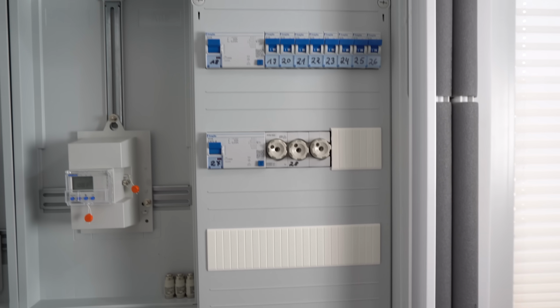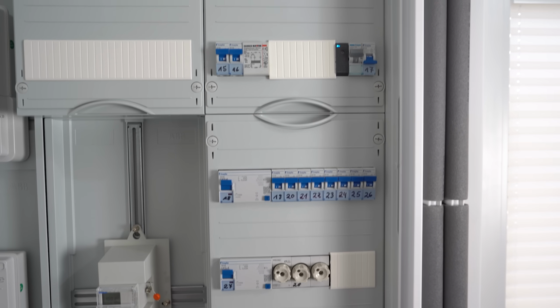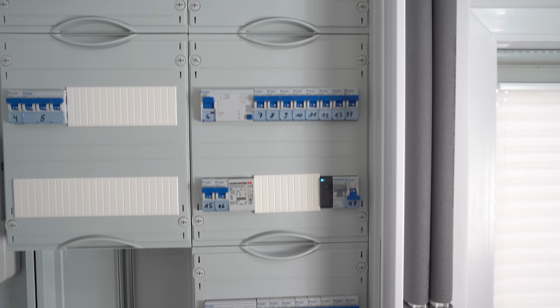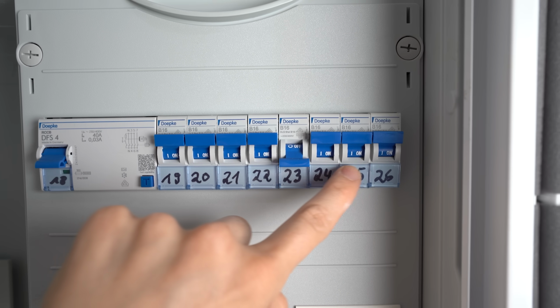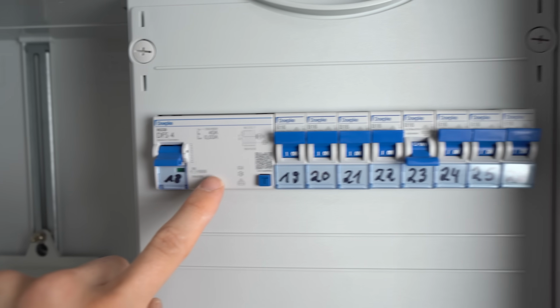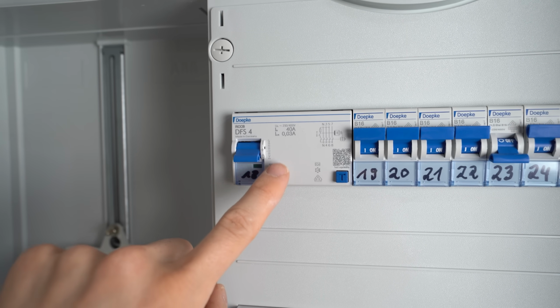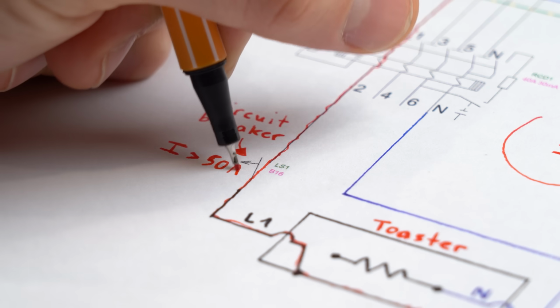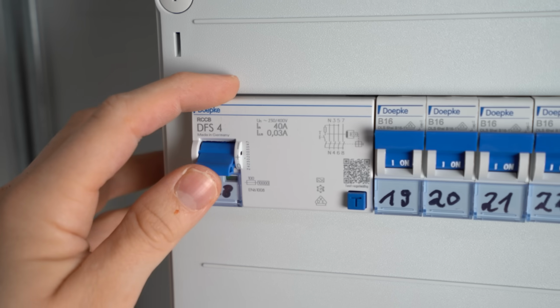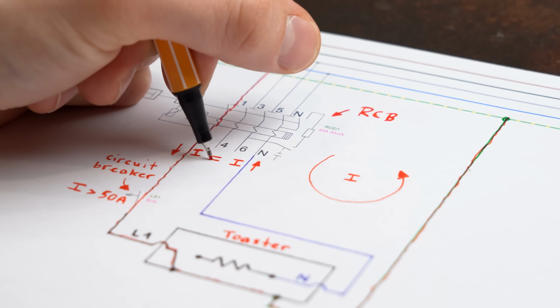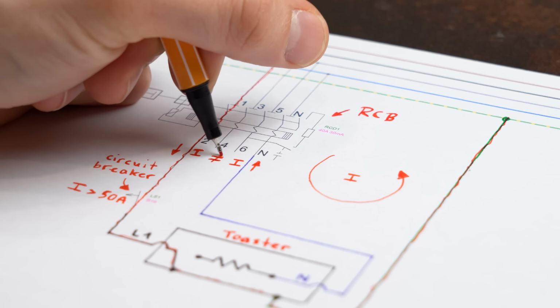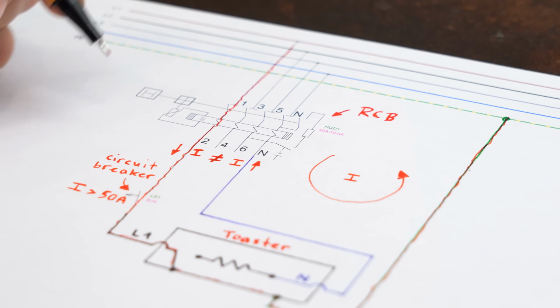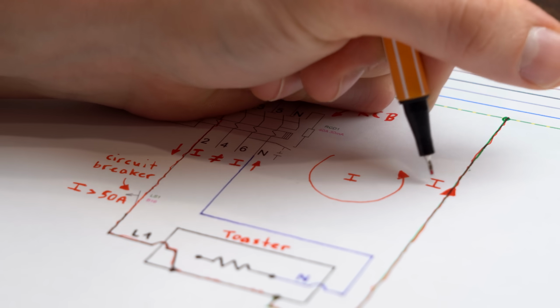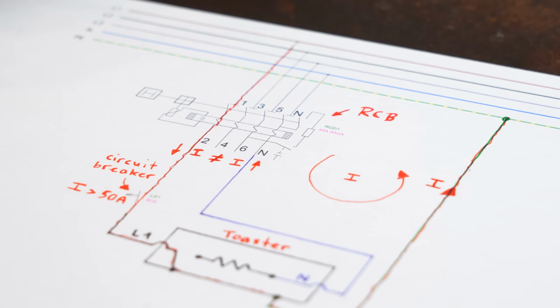This cutout happened because the protective devices inside my distribution panel tripped, which are for one a normal circuit breaker and also an RCB. Now the circuit breaker tripped because of the big current flow, and the RCB tripped because the current flowing through live and neutral were no longer the same value, since this time current flowed through the ground wire.